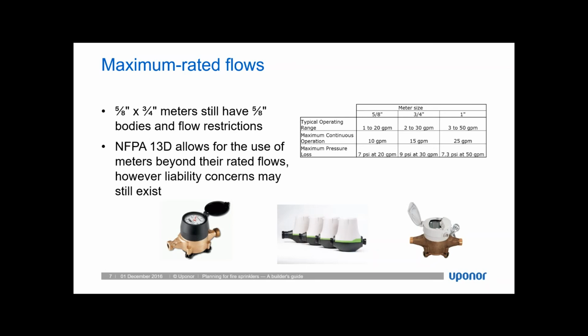It's important to note that 5/8 by 3/4 inch meters still have a 5/8 body with the same flow restrictions as a 5/8 meter. Now, as you can see, I'm pointing this out because a 5/8 meter has a typical operating range of only 1 to 20 gallons per minute. Our typical sprinkler demand of 26 gallons per minute exceeds this 20 gallon per minute range. Now, there has been testing done by the Fire Research Foundation to prove that these 5/8 meters actually are more than capable of flowing beyond this maximum allowed flow. As long as the additional pressure loss, which can be significant, is incorporated into the design, their conclusion was there's no reason that you would not be able to use a 5/8 meter on a typical sprinkler system.